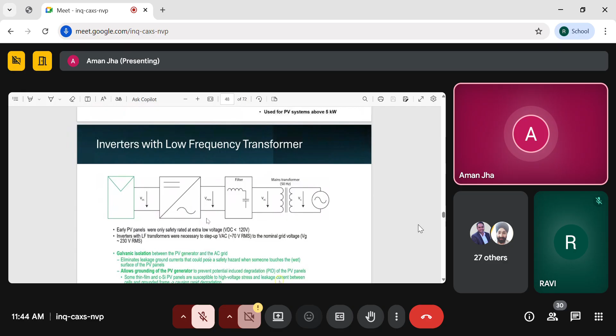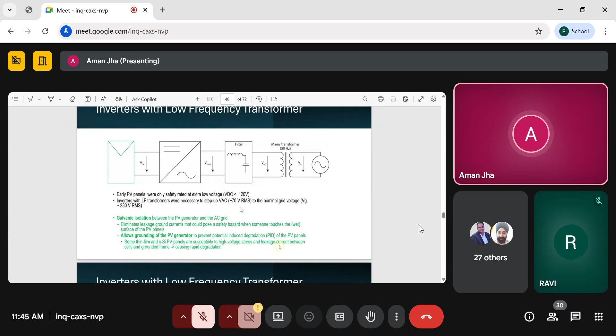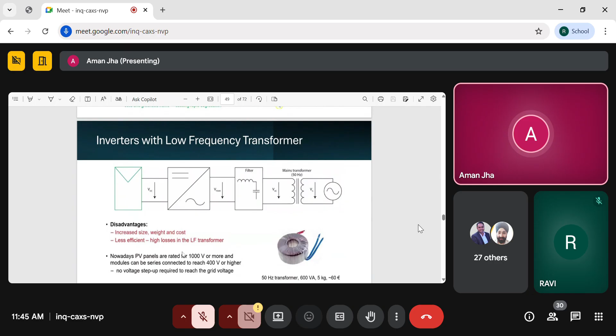Normally the advantage here is that we get galvanic isolation between the PV generator and the AC grid. That is the good part, but at the same time, the main transformer is bulky and heavy, so you get increased size and weight, and the cost will be more. This is the reason nowadays PV panels are rated for 1000 volts and more. So normally we go with the grid without a transformer.